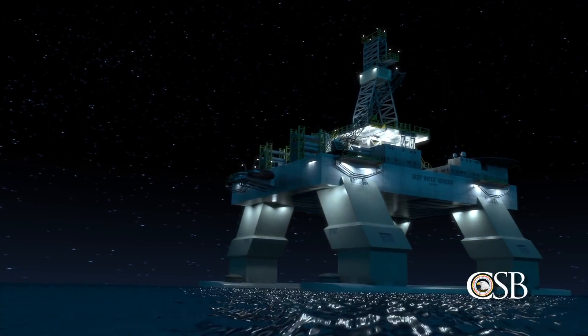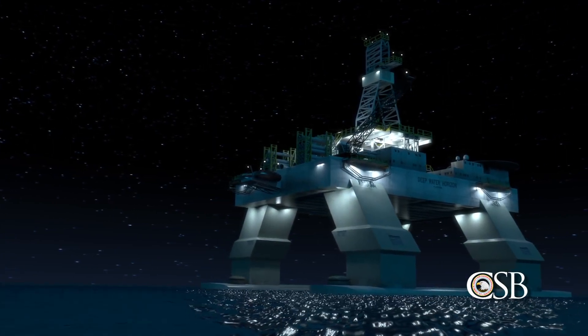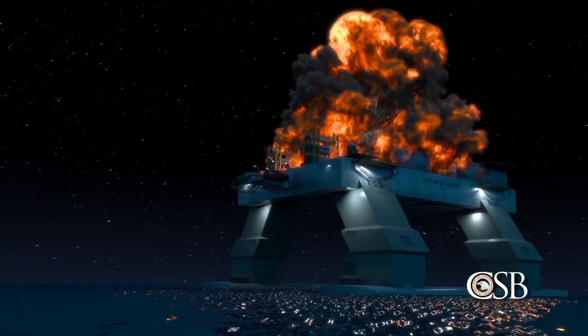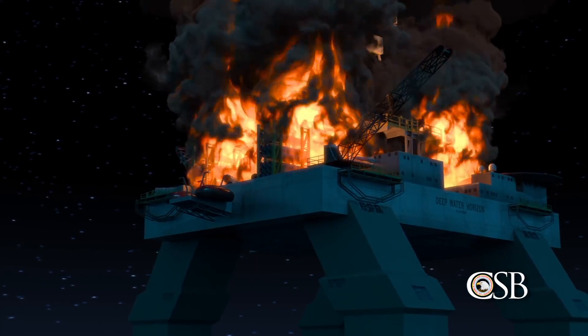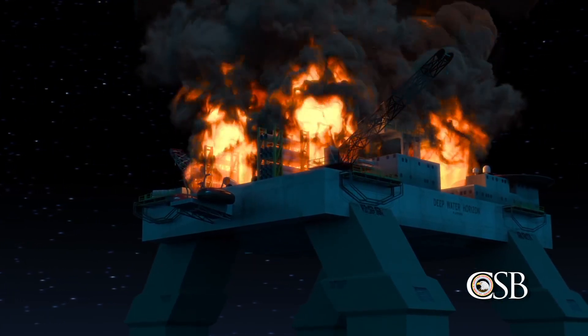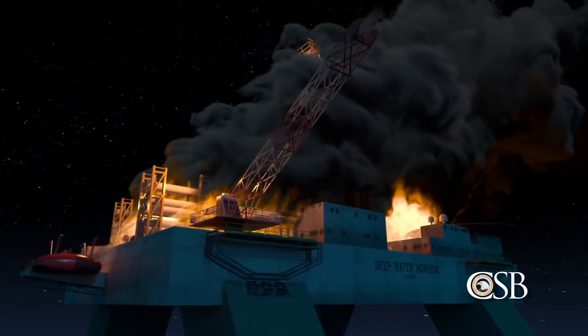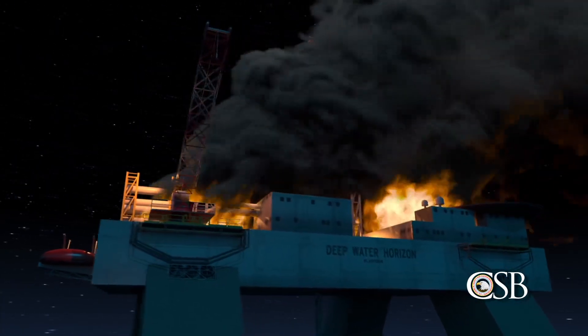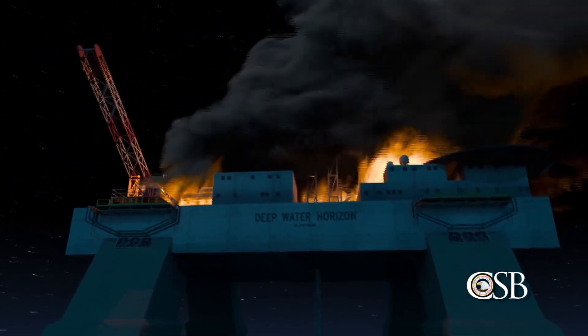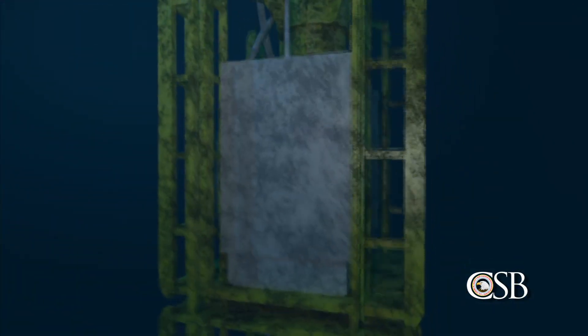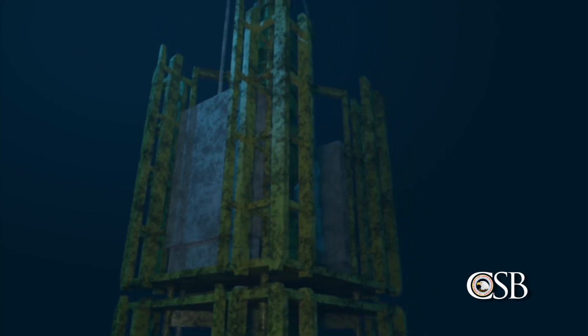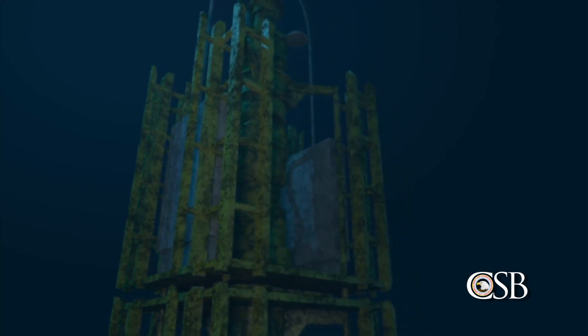At approximately 9:49 PM, the flammable hydrocarbons found an ignition source when the first explosions shook the Deepwater Horizon. With the drill pipe buckled, the explosion and subsequent loss of electrical and hydraulic power from the rig likely activated an automated system on the blowout preventer known as the AMF Deadman, which closes the blind shear ram and cuts the drill pipe. This emergency system is designed to activate when electric power, hydraulic pressure, and communications from the rig have been lost.